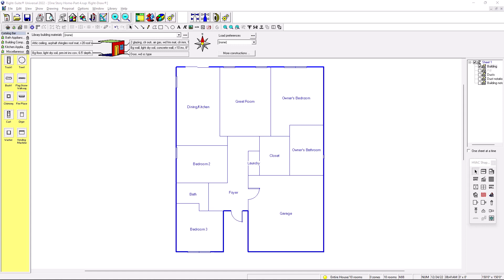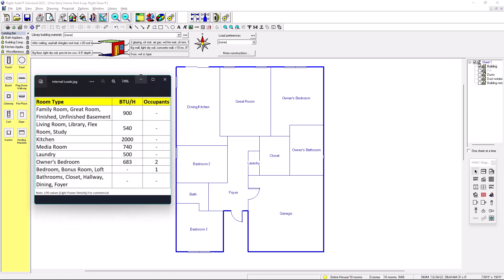We're going to put the internal loads into our room layout. On the left side I have a table — this depends on the client. For example, we're going to put a load of 900 BTUs per hour and no occupants for family room, great room, finished basement, and unfinished basement. Another client might want 1000, another 800 — it depends. This is based on Manual J / ACCA standards.